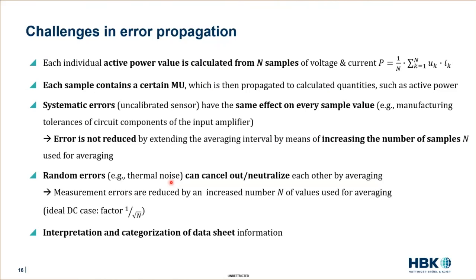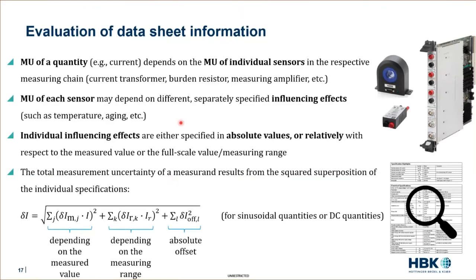And as you can see from all those things, it is really important, if you read through the data sheets, that the interpretation and the categorization of error influences is really important. It's one of the bases. And we can take a closer look here again. So if we take, for example, only one quantity, the current, then in order to measure the current, we have a lot of different sensors in the measuring chain. For example, the current transducer, over here the burden resistor, and the input amplifier, or the power card in this case. And all of them contain measurement uncertainty, and of course, in addition to the environmental conditions.